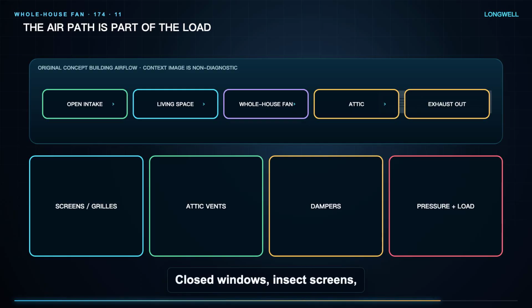Closed windows, insect screens, restrictive grills, blocked attic vents, stuck dampers, and added air sealing can change pressure and motor loading. Correct the building level restriction rather than treating the motor as the only suspect.